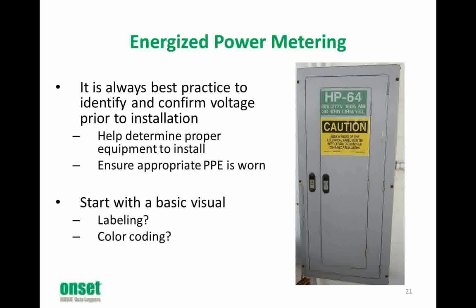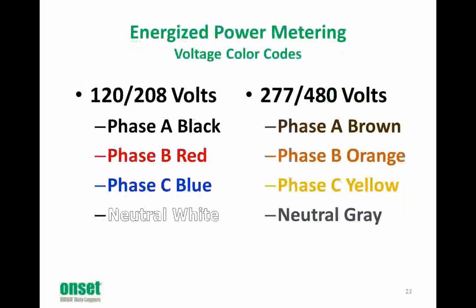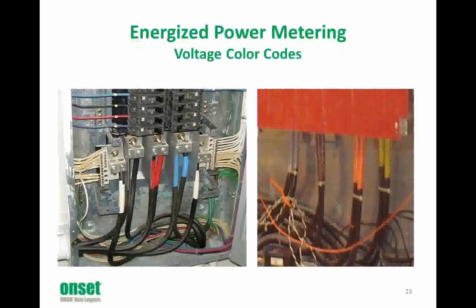Here we can see if there is any color coding to help confirm our voltage assumptions. Typically, black, red, and blue are used to identify 120/208 volt systems, and brown, orange, and yellow are used to identify 277/480 volt systems. Here are examples of each voltage configuration. On the left we have a 208 volt panel board, and on the right we have a 480 volt panel board.